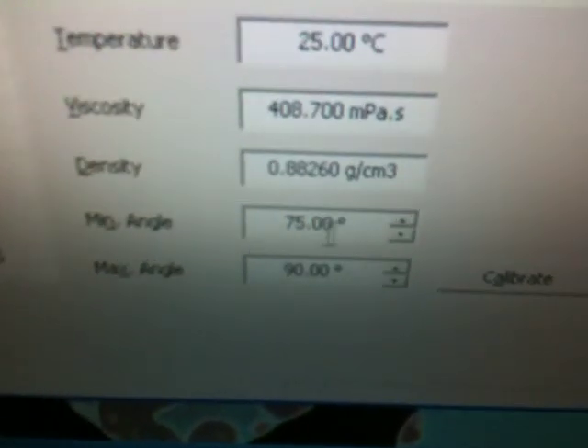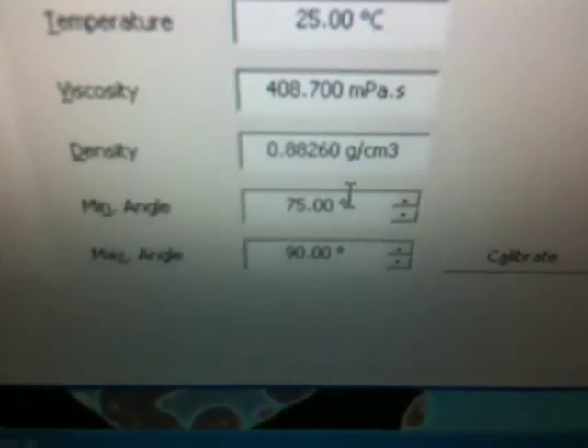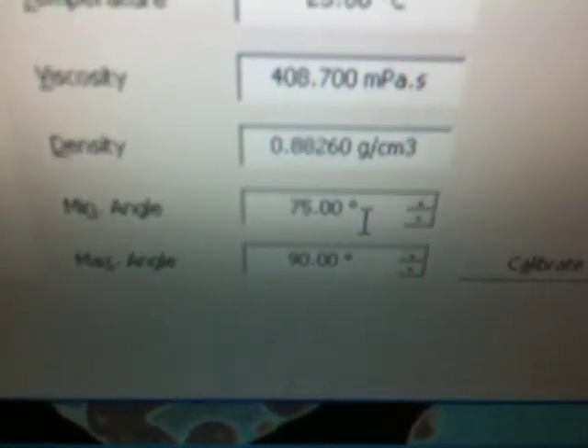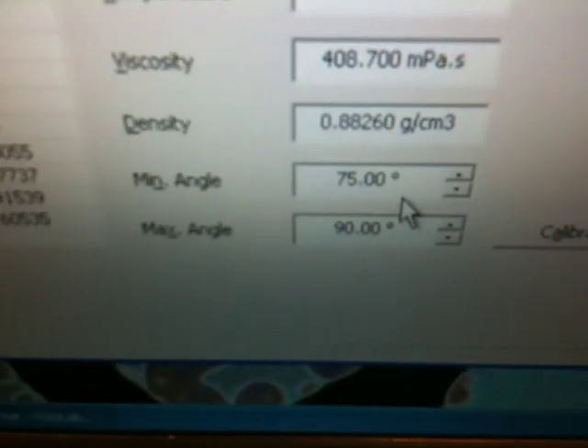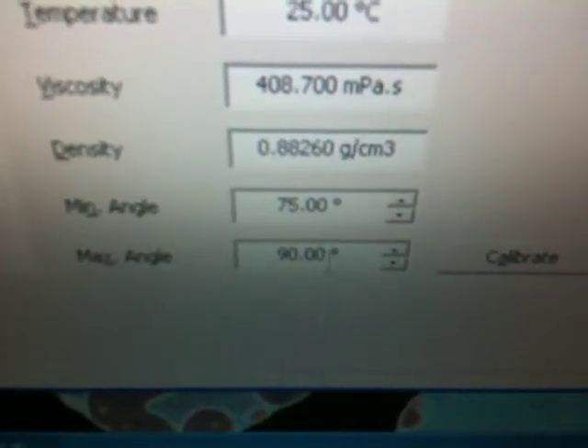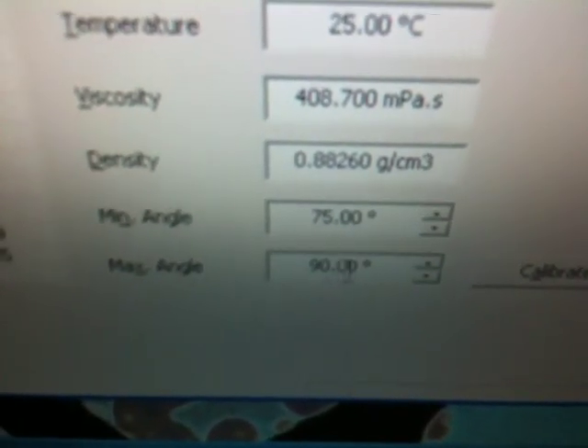These two, because the bead can fall out and can get stuck in the top, don't drop this below 75 when you're calibrating it. Just leave it at 75. You want to get as many angles to calibrate at as possible, so you do the max at 90. So just leave this one at 90. You can leave this at 75 for whatever calibrations you're doing.